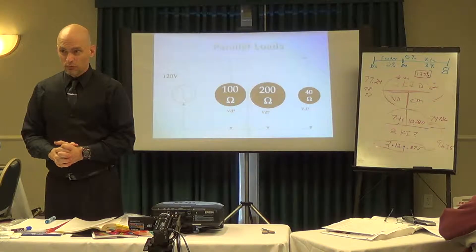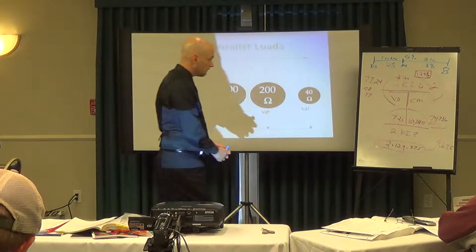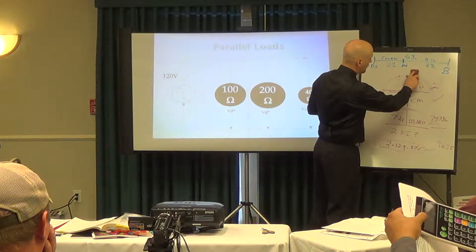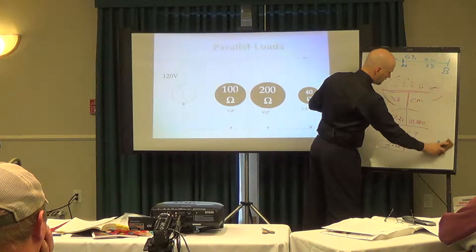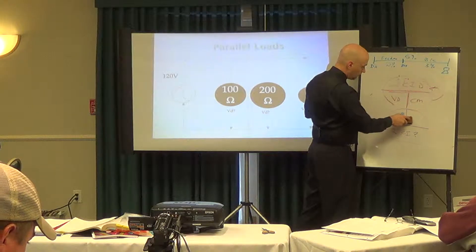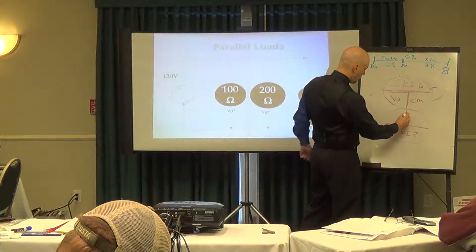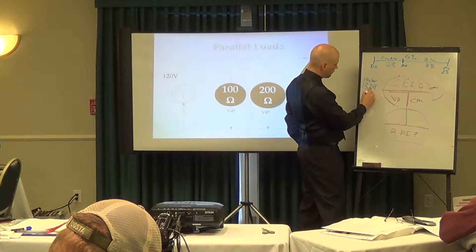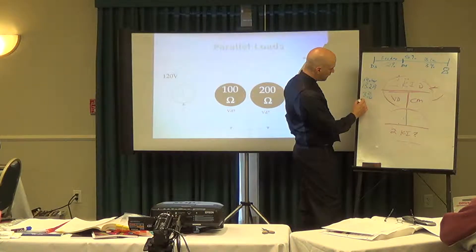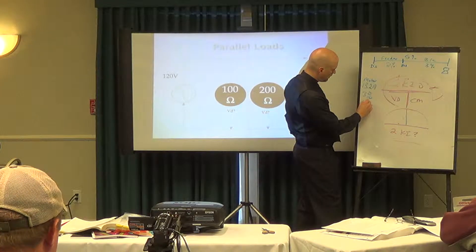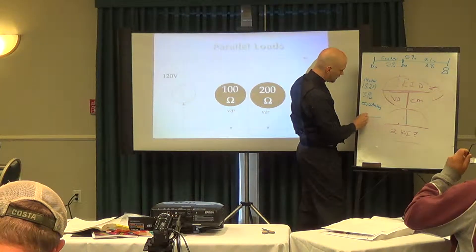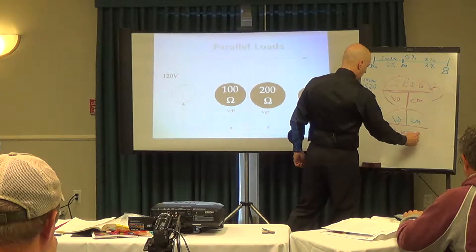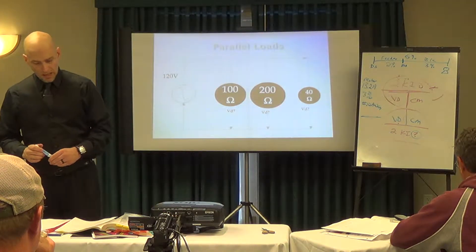We'll work another one just like that since I kind of messed up this one just to make sure that this is solid so that it's clear. And if you have one of these on the test, it would probably be this one right here. So if you're looking for a wire size, that's exactly the same. They give you one on the test that is kind of the same deal, but they don't give you enough to make it work out. See if I can remember it here. It's going to be a motor that's 13.2 amps on this motor load. And it's a branch circuit, so you don't want to lose more than 3%, and they give that to you. And I think they give you the wire size as a number 10, and that's all they give you. They're asking you what's the maximum distance then that number 10 can be given that amount of information. So this is voltage drop, circular mils, and 2KID again, the distance we're looking for.